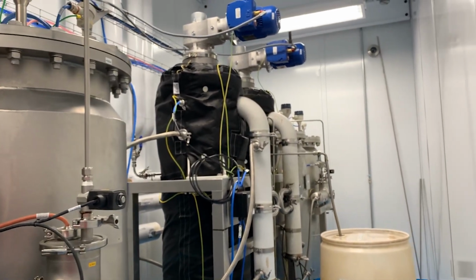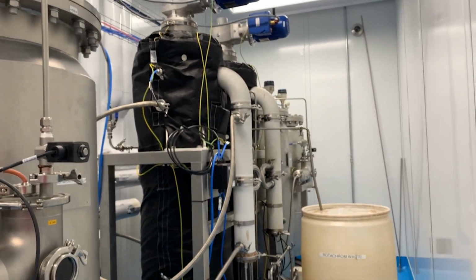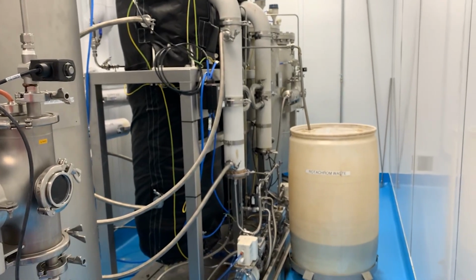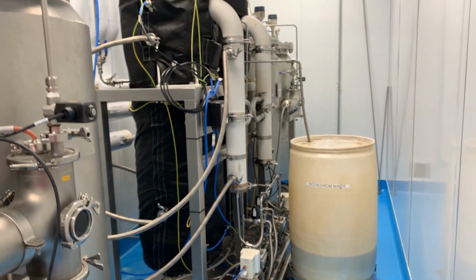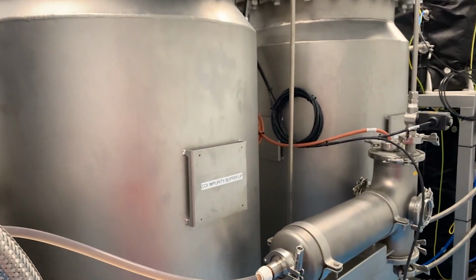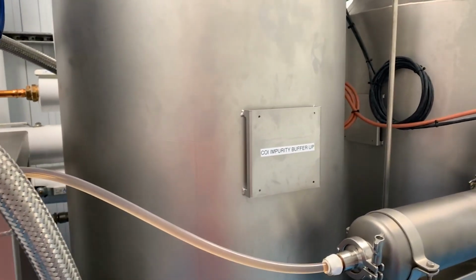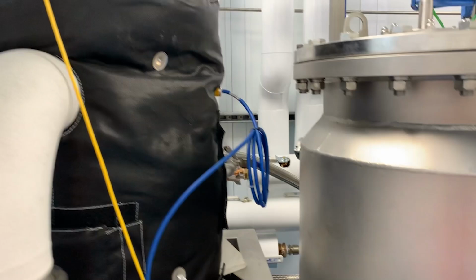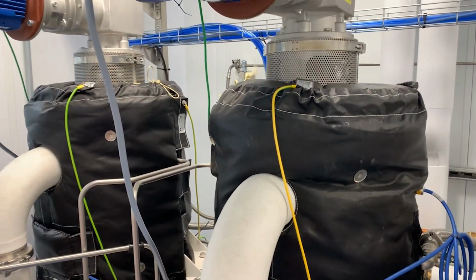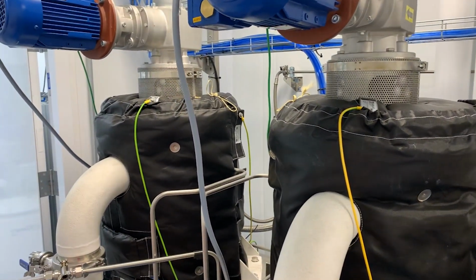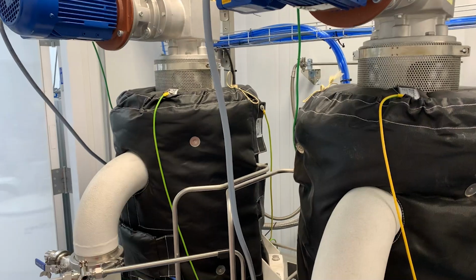The first 2 evaporators are utilized in this case for the fractions that contain the compounds of interest. As the fraction comes out of the ICPC, it has about 90% solvent. The solvent level needs to be reduced, and this setup takes the solvent level down to about 25–30%. Most of the methanol comes out from the system.